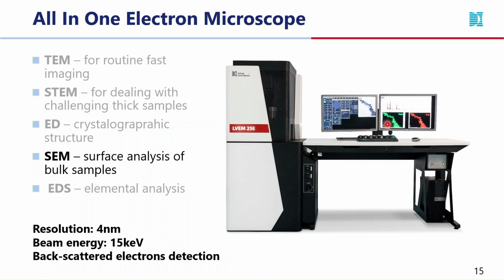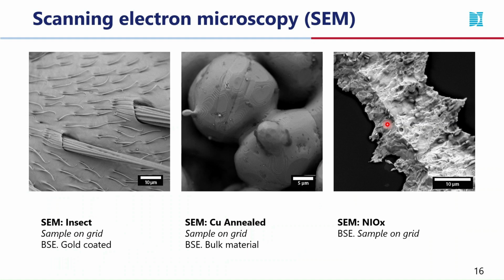Let's start with SEM. The unique combination of transmission modes and SEM is so popular with customers of LVEM5, the smaller brother of LVEM25E, that we decided to equip the new generation of LVEM25 also with the SEM mode with the detection of backscattered electrons. It allows not only the investigation of diverse non-transparent bulk samples, but we can also use SEM for imaging of thin sections, which provides us with another dimension of imaging possibility.